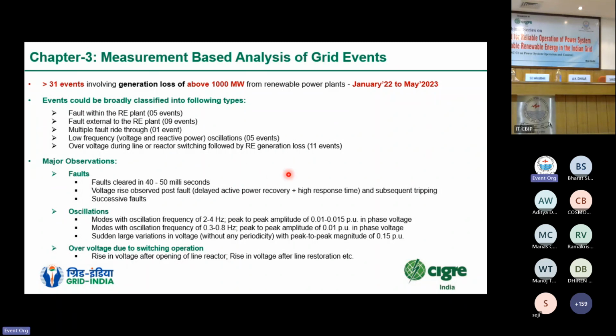So some major observations: there have been no delayed fault clearance cases. Mostly faults have been cleared within 40 to 50 milliseconds. Then there has been a voltage rise immediately after the successful clearance of the fault. And coming to oscillations, we can categorize them into 3 categories. The first one has an oscillation frequency of 2 to 4 hertz and an amplitude of around 0.01 to 0.015 per unit.